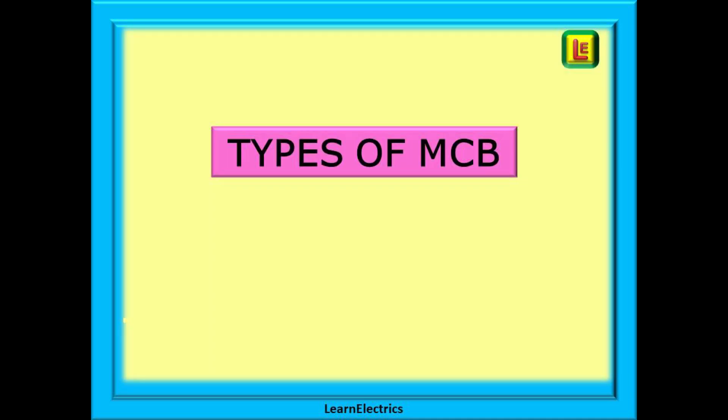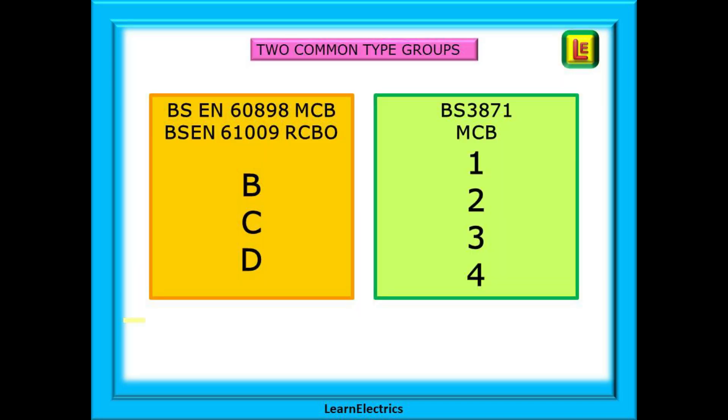Let's begin with a look at the different types of MCB. There are two type groups: the BS EN 60898 MCBs and BS EN 61009 RCBOs that use the designation types B, C and D for the most popular types. And then the older but still in use BS 3871 MCBs with the type numbers 1, 2, 3 and 4.